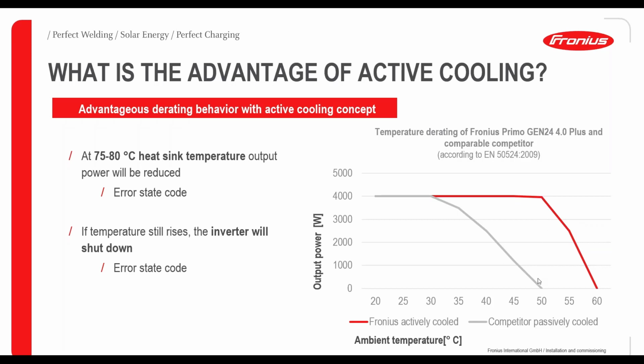So within this temperature range, we can secure the maximum yield of our inverter and also the longest lifetime of our inverter. On the left side, I quickly want to show you, we have it written down here, at 75 to 80 degrees heatsink temperature, the power will be reduced. This is about 50 degrees ambient temperature. If the temperature is rising, the inverter will shut down eventually. So that's the big reason why we at Fronius set to active cooling so much.